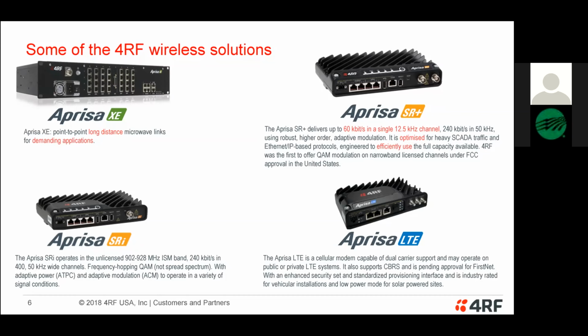We do this through the use of QAM, or quadrature amplitude modulation, which allows us to pack a lot more data into the same channel you used to have. Let's say you had, for a good example, an MDS 9710, SD9, or SD4, where maybe you were able to do 9600 baud or 19.2 kilobits per second across that licensed channel. We can pretty much straight away, just by replacing the radios, come up with 6 to 7 times more capacity on that same link.